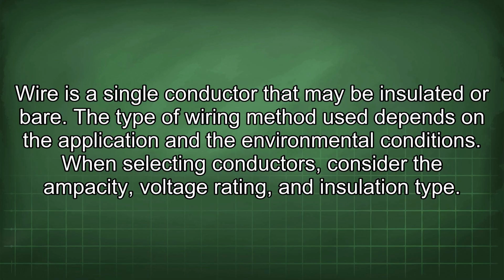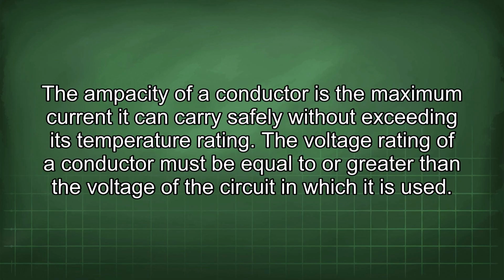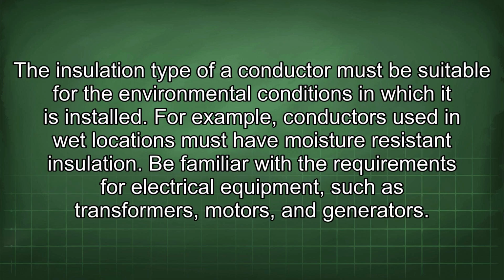When selecting conductors, consider the ampacity, voltage rating, and insulation type. The ampacity of a conductor is the maximum current it can carry safely without exceeding its temperature rating. The voltage rating of a conductor must be equal to or greater than the voltage of the circuit in which it is used. The insulation type of a conductor must be suitable for the environmental conditions in which it is installed. For example, conductors used in wet locations must have moisture-resistant insulation.